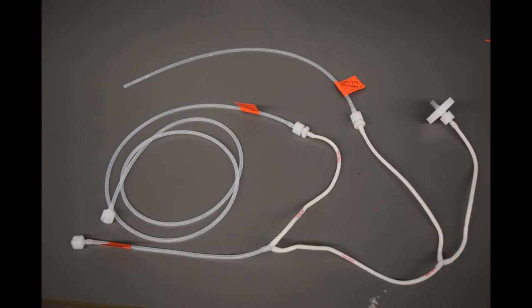Next, let's set up the sample tubing. As shown in the picture here, there are two sections of Y-pinch tubing connected together with a branch of one Y connecting to the base of another. From left to right, we start with a small section, approximately 15 centimeters, of 1/8-inch outer diameter tubing with a male luer lock on one end and the other connected to the base of one Y pinch tube. The left branch of this first Y has a female luer lock barb which connects to a male luer lock and the tube to the bioreactor or source, which is approximately 100 centimeters long. The other end of this section has a male luer lock to attach to a sampling probe on the bioreactor. The right branch of this first Y attaches to the base of the second Y.